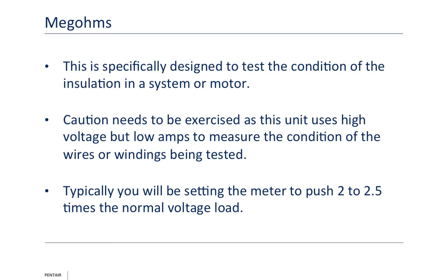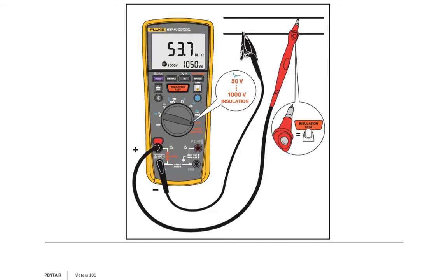When you start to get down to, say, 200,000 or less, depending upon the motor, it's a concern. For example, Baldor doesn't like to see their insulation on a three-phase motor be less than 5 million ohms. That causes concern for them. Submersible pumps, if it gets below 200,000 ohms, not 5 million, then we're concerned. So always refer to the factory manual.